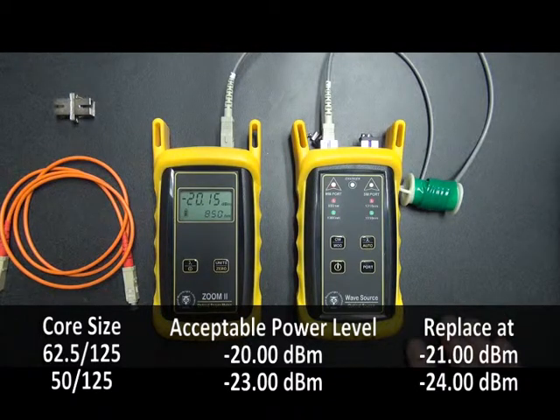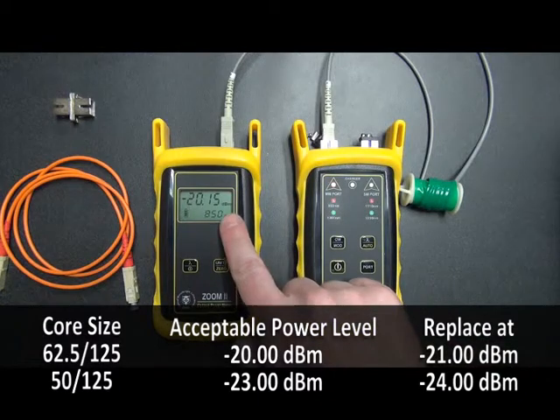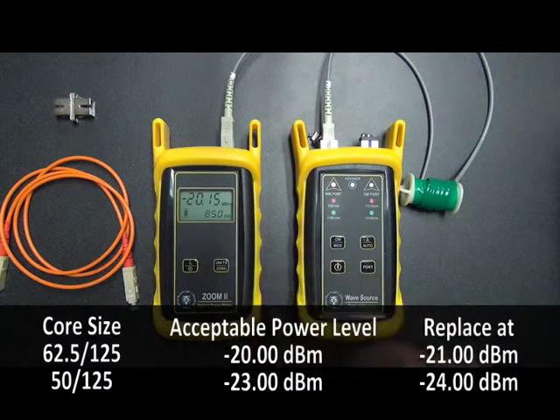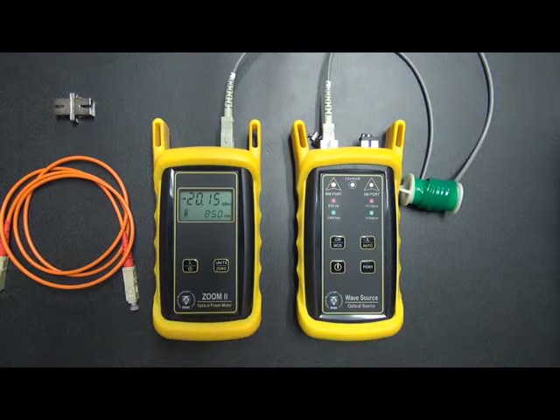Now the reading could be a little higher, a little lower, but it's going to be close. In this case, it's a little bit lower, but it's still acceptable. If we're reading a little bit lower than minus 21, then we may want to consider replacing the patch cable for referencing. But in this case, we have a good patch cable here.